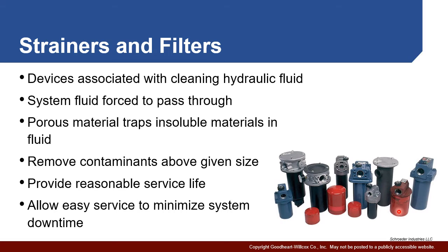They're going to be constructed of a porous material, right? Since porous is essentially filled with holes, that's going to try to prevent or trap the insoluble materials, so any solid materials that won't break down. They're going to be rated for a certain size, so essentially any contaminant that's larger than that should get trapped. And the idea is for them to last for as long as possible. Filters can be expensive. Shutting down the system can be problematic. So you want them to have a certain service life.